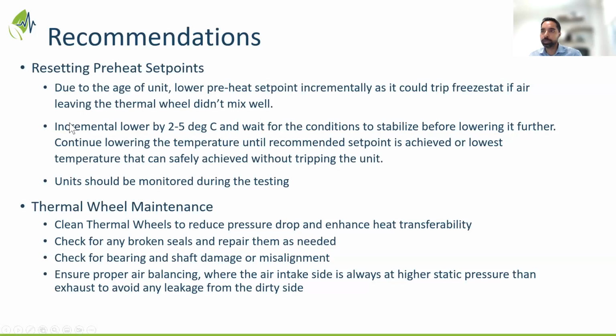So we talked about most of the recommendations. I just want to quickly touch on them. So, resetting the preheat set points. For older facilities, what we're recommending is to do those incrementally, so you can test your systems and their boundaries and don't end up with a freezestat tripping, because you don't want a sudden movement. But you definitely want to try the outer boundaries, how far you can push the existing systems. For the newer facilities, whatever your manufacturer's recommended set points are, it should be able to achieve that with no issues with any of the frost conditions or any other potential dangers of freezing the systems.